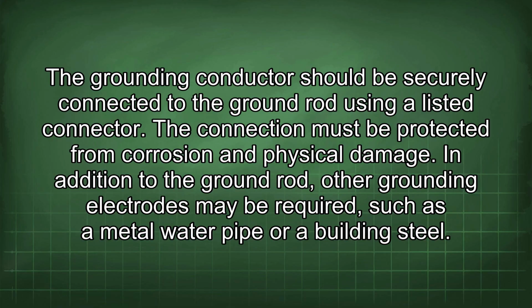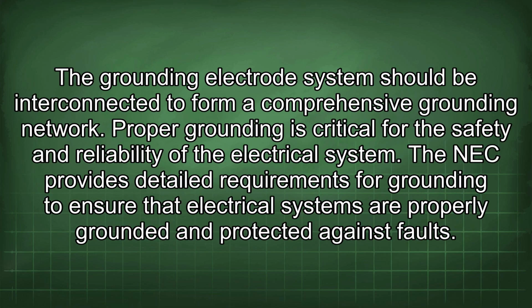In addition to the ground rod, other grounding electrodes may be required, such as a metal water pipe or building steel. The grounding electrode system should be interconnected to form a comprehensive grounding network. Proper grounding is critical for the safety and reliability of the electrical system. The NEC provides detailed requirements for grounding to ensure that electrical systems are properly grounded and protected against faults.